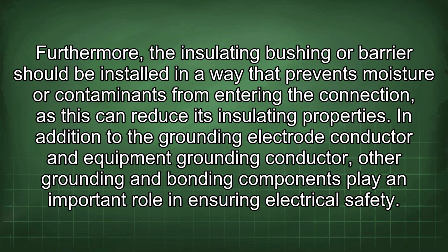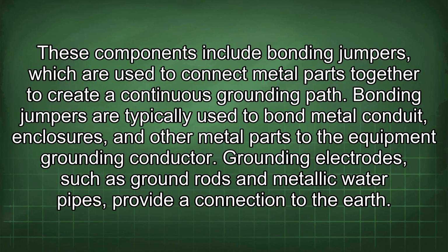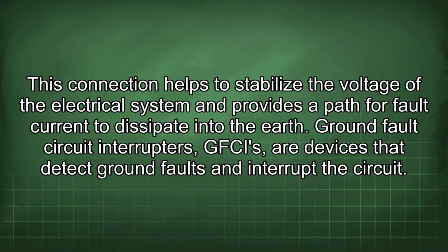In addition to the grounding electrode conductor and equipment grounding conductor, other grounding and bonding components play an important role in ensuring electrical safety. These components include bonding jumpers, which are used to connect metal parts together to create a continuous grounding path. Bonding jumpers are typically used to bond metal conduit, enclosures, and other metal parts to the equipment grounding conductor. Grounding electrodes, such as ground rods and metallic water pipes, provide a connection to the earth. This connection helps to stabilize the voltage of the electrical system and provides a path for fault current to dissipate into the earth.